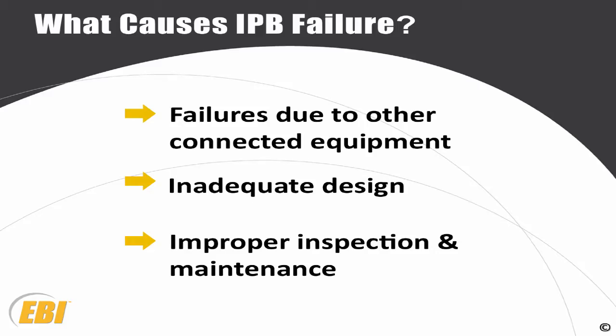What causes IPB failure? We can break this down into three basic groups. The first one is failures due to other connected equipment, such as your generator, or a transformer, or a PT cubicle. The second one is inadequate design that is inherent in pretty much every isolated phase bus designed by all the OEMs. They have weak spots in their designs. And then the third one is improper inspection and maintenance. We have found out that pretty much 50% of all the IPB failures fall under the third category of improper inspection and maintenance.